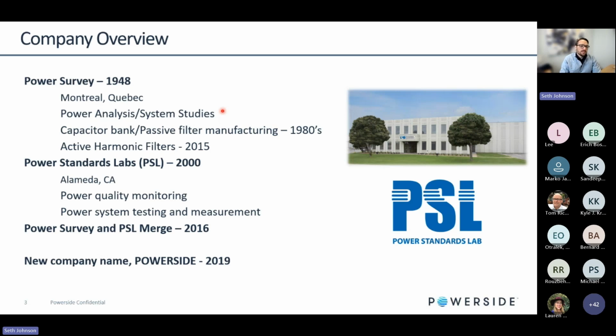From there we transitioned into capacitor bank and passive filter manufacturing, which many of you are familiar with. A big part of our business, of course, is both low and medium voltage power factor correction and harmonic filtering. Then around 2015 we got into power electronics, specifically in the active harmonic filter domain. And you'll see in a case study I present later how we use the active harmonic filter with this power systems analysis program.